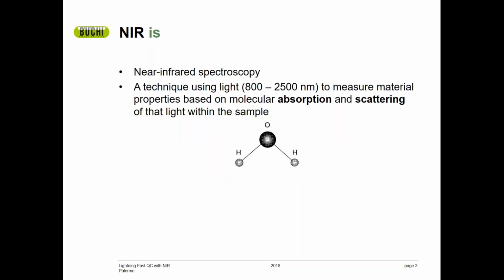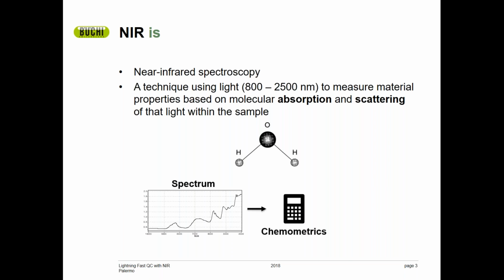So what is NIR? NIR is a technique that uses low-energy light, typically on the order of 800 to 2500 nanometer wavelength, to measure material properties like identity or composition. The measurement principle is based on the fact that molecules vibrate. When the vibration of the molecule matches that of the incident light, light is absorbed, giving us a characteristic spectrum. Particles also scatter light in unique ways, providing evidence of physical characteristics to the signal and further enriching the spectral fingerprint. Chemometrics is the way that we can relate that spectrum and its information to the qualities of interest, generating our reports.